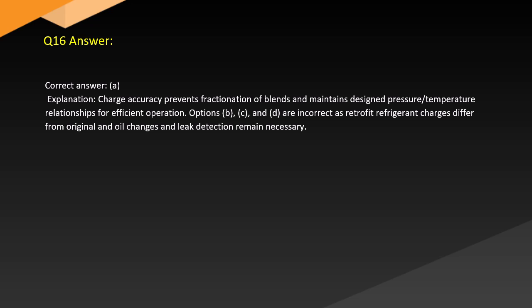Answer. Correct answer, A. Explanation. Charge accuracy prevents fractionation of blends and maintains design, pressure, and temperature relationships for efficient operation. Options B, C, and D are incorrect as retrofit refrigerant charges differ from original and oil changes and leak detection remain necessary.